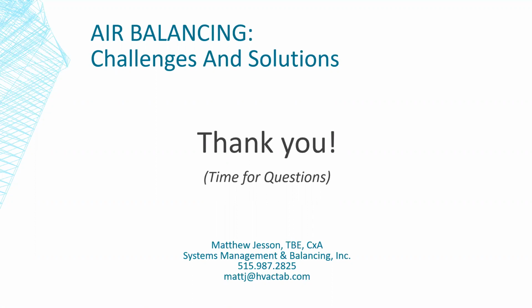The first one was, is there a minimum number of traverse measurement points when using a duct traverse? Yeah, that's a great question, and there are TAB manuals and standards. My company is in AABC, the Associated Air Balance Council, and their standards would provide the minimum requirement for different sizes of duct. So it all depends on the size of duct. As a general rule of thumb for most reasonable duct sizes, you want to go somewhere between 4 and 6 inch spacing when setting up a duct traverse.